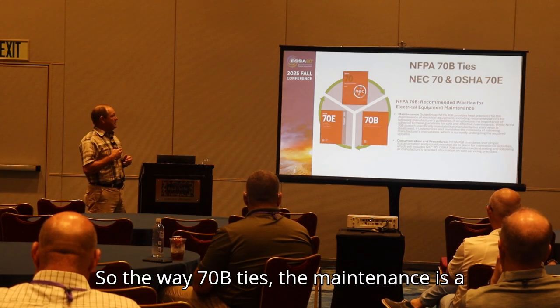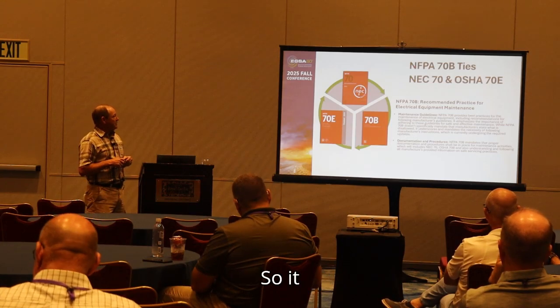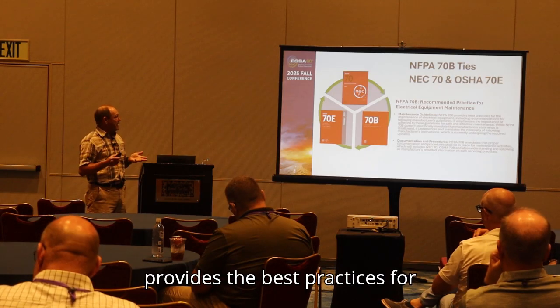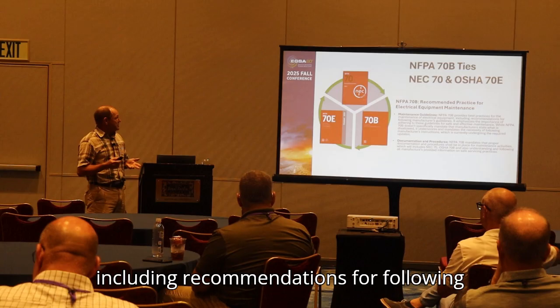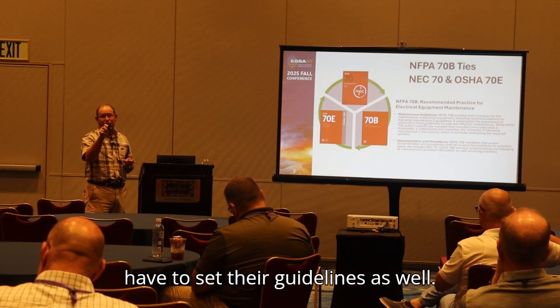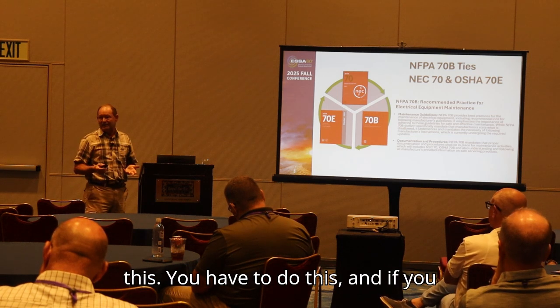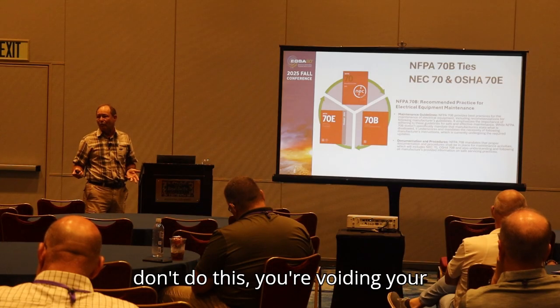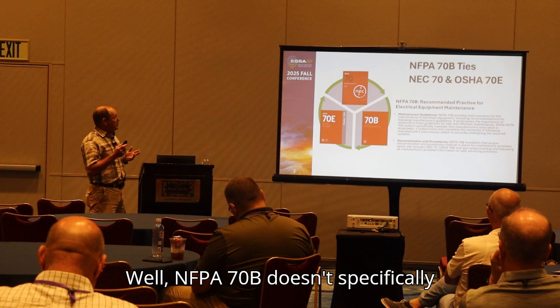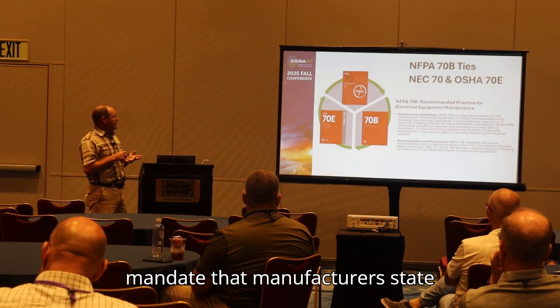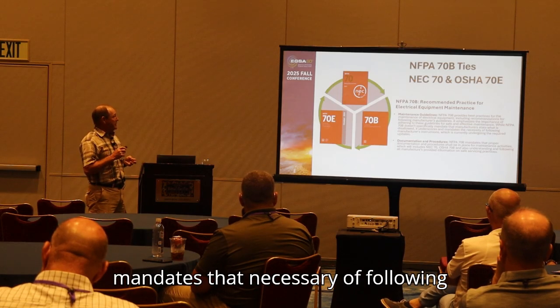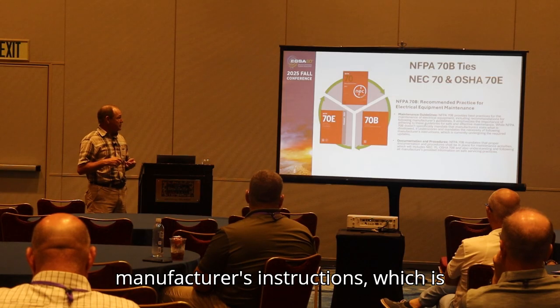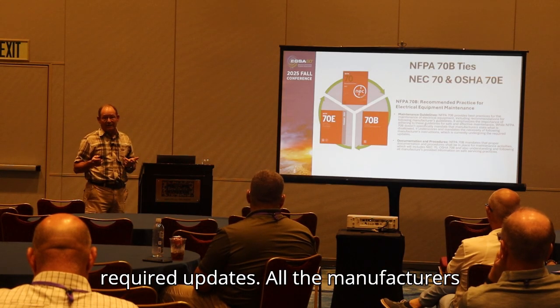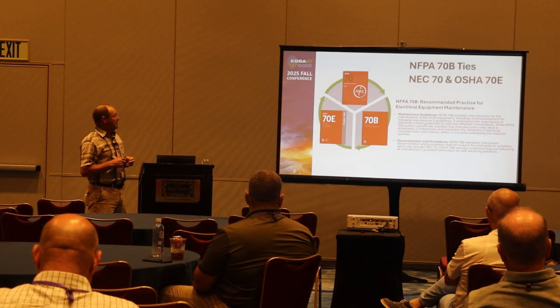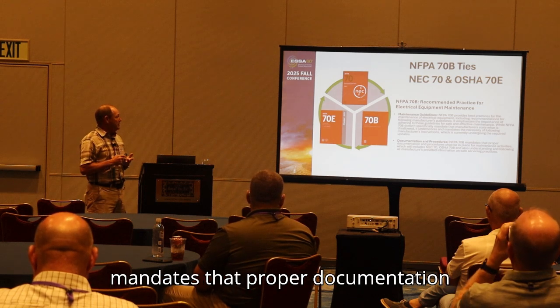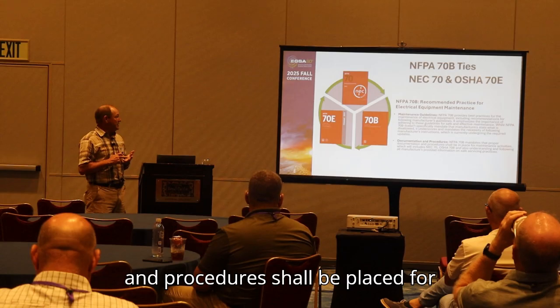The way 70B ties in, maintenance is a big part of what EGSA is about. It provides best practices for maintenance of electrical equipment, including recommendations for following manufacturers' guidelines. Manufacturers have to set their guidelines as well - that's part of where they're tied to this. You have to do this, and if you don't, you're voiding your warranty. While NFPA 70B doesn't specifically mandate what manufacturers state is disallowed, it underscores and mandates the necessity of following manufacturer's instructions, which is currently undergoing a lot of required updates - all the manufacturers are. Documentation and procedures: 70B mandates that proper documentation and procedures shall be in place for maintenance activities.